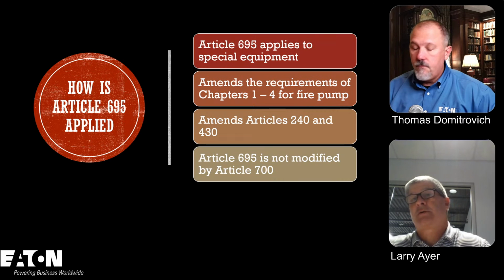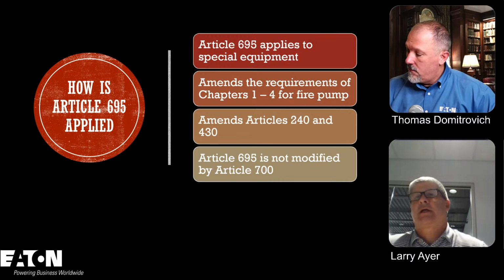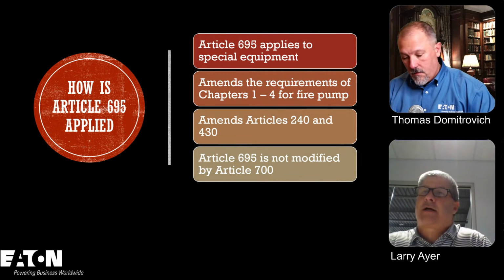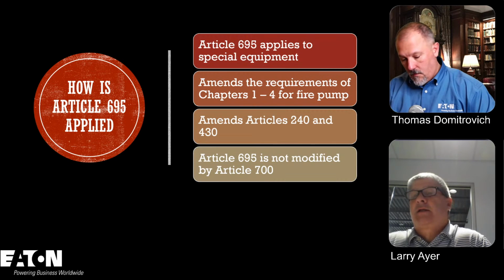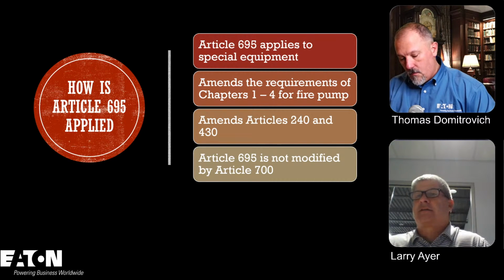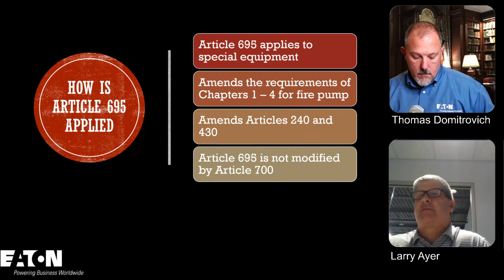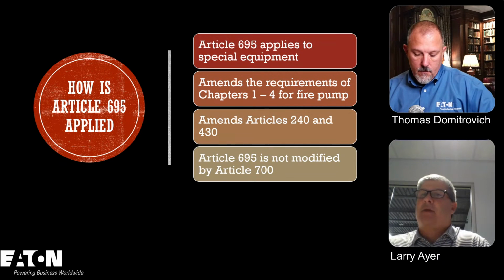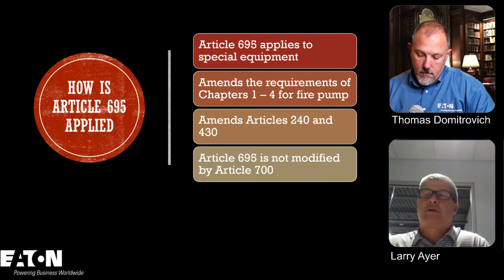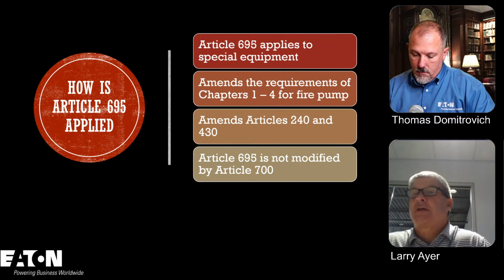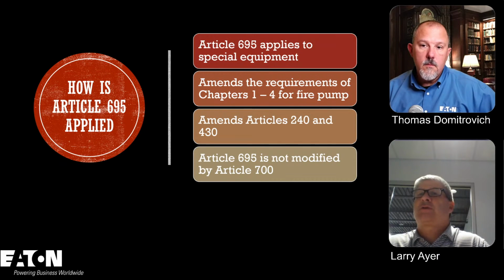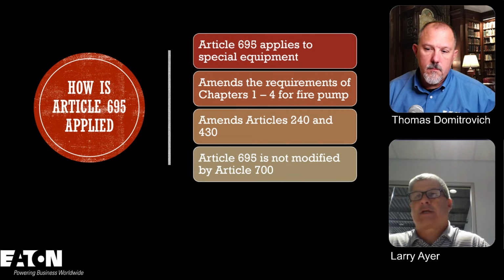That's correct. Yep. And so what you have to look at is, typically, chapters 1 through 4 of the code are the key, right? They tell you how to size wires, how to protect wires and overcurrent devices, when you need GFCI and things like that. And when you get up to 695, fire pumps are special equipment. They modify 1 through 4. It's just like motors. We do not protect fire pump conductors at the ampacity that you typically would think of in Article 240. And so we do some different things up there. We're not required to have ground fault protection on these circuits. So we need to modify those things. And that's why, when you put the slide up there, 695 is going to amend the requirements in chapters 1 through 4.